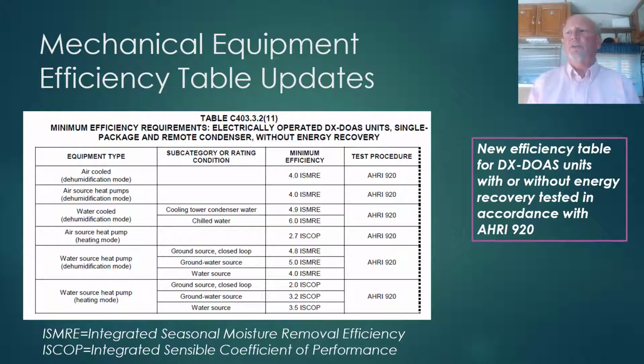Often these DX DOAS systems are used when we have large amounts of outside air that we're bringing into our DOAS system. Especially now that DOAS has been expanded to Group A occupancies, banquet halls, conference auditoriums, gymnasiums. There may be occasions where you have an event with high ventilation requirements, and it's a humid day outside, so you're bringing in a lot of moist air, increasing the humidity in the conditioned space and adding that latent load to your heating and cooling equipment. So an option is to go ahead and remove or dehumidify that moisture prior to delivering that air to the space.